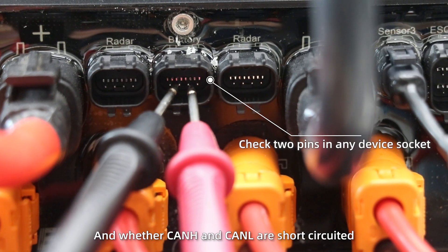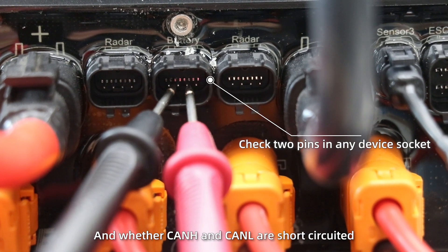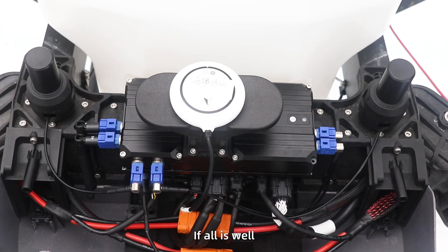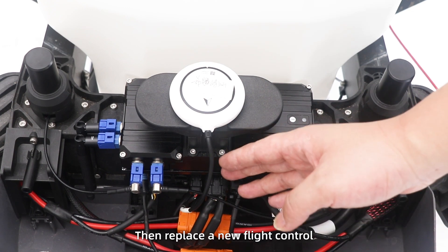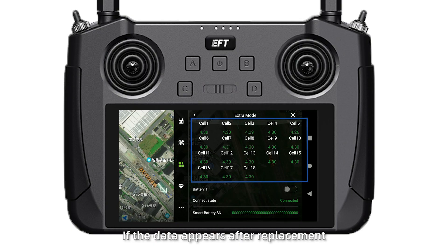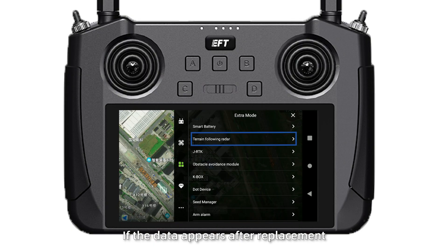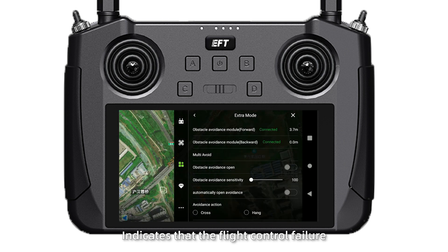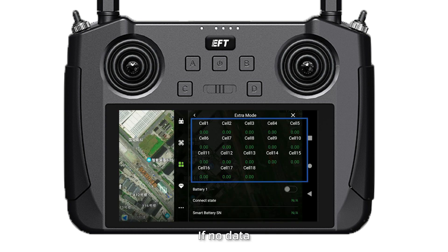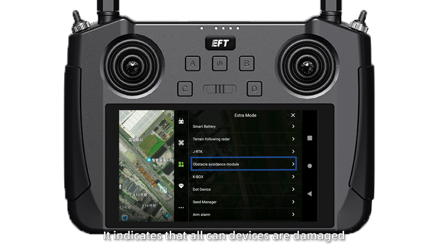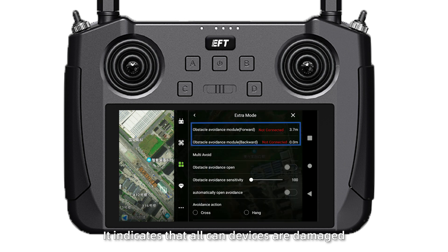Also check whether CAN high and CAN low are short-circuited. If all is well, then replace with a new flight control. If data appears after the replacement, it indicates flight control failure. If there is still no data, it indicates that all CAN devices are damaged.